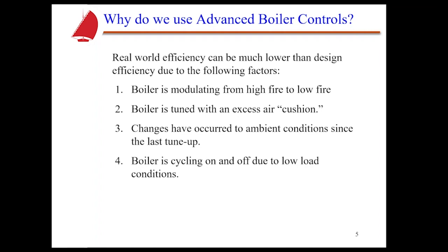Now, what also affects this air-fuel ratio can be ambient conditions. We all know that during the winter, we have colder combustion air, and that air is going to be more dense, more oxygen rich. However, in the summertime, when we're much warmer, we don't have that density. So we either have to do another tune up there, or again, we're going to have to make sure that we have plenty of air during the summer months so that we don't go rich.